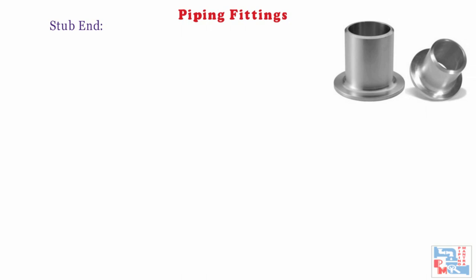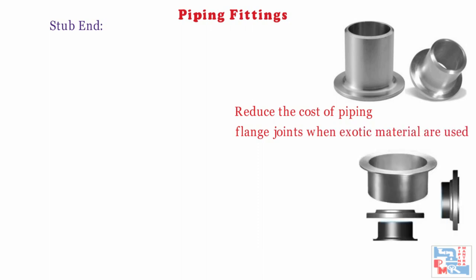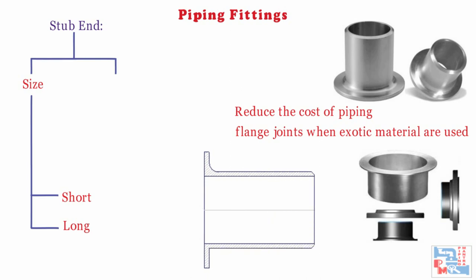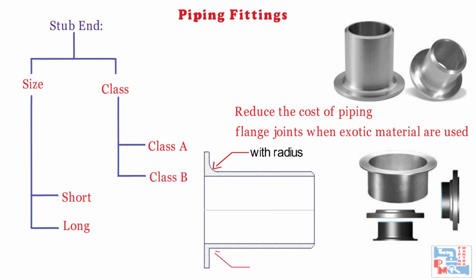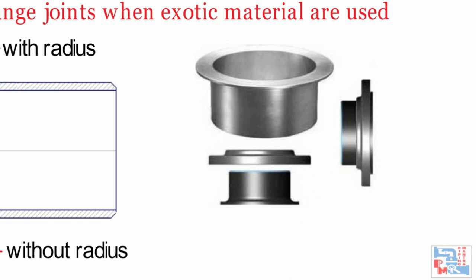Stub ends are used with backing flanges for flange joints to reduce the cost of piping. When exotic materials are used in piping, stub ends connect loose flanges in the piping. There are two types based on size: short stub end and long stub end. And two types based on class: Class A with radius and Class B without radius at the corner. Stub ends can be used with slip-on flanges, and we must ensure sufficient clearance between the weld of pipe to stub end and flange.